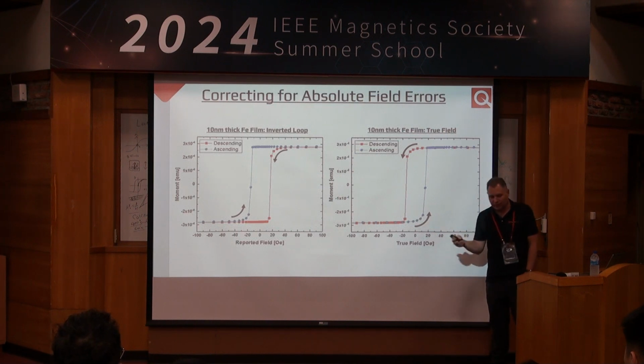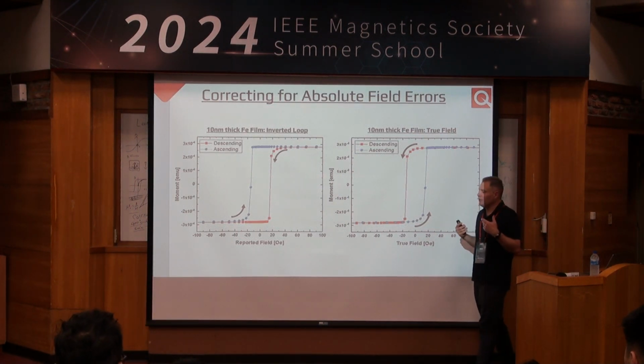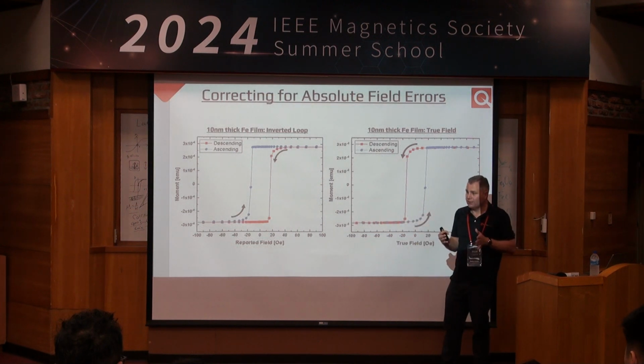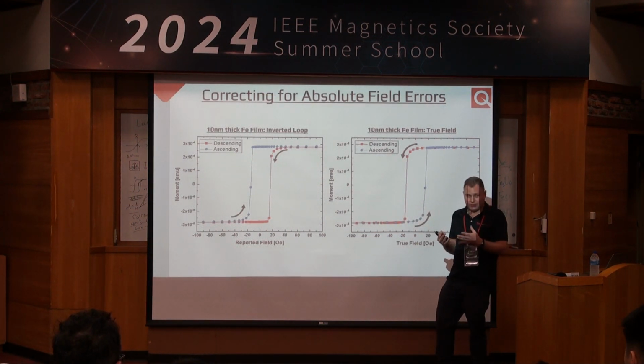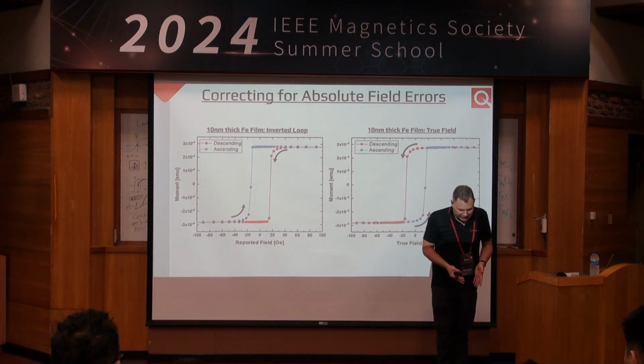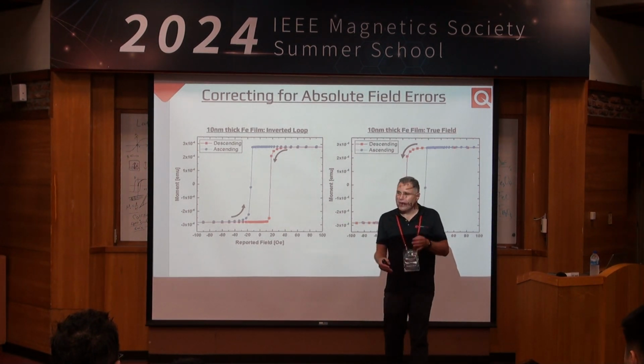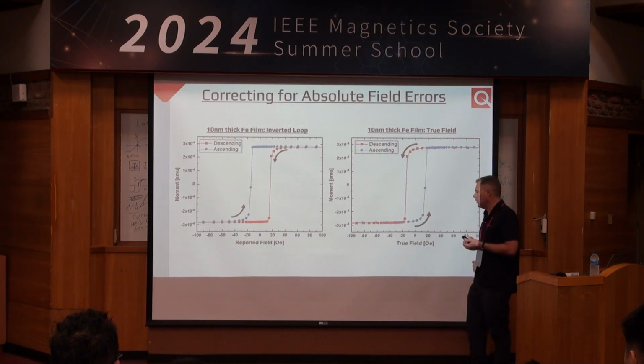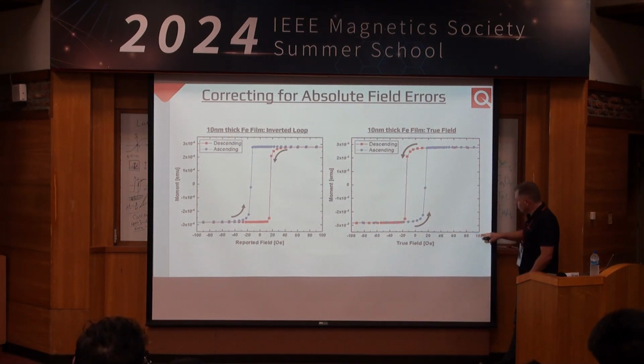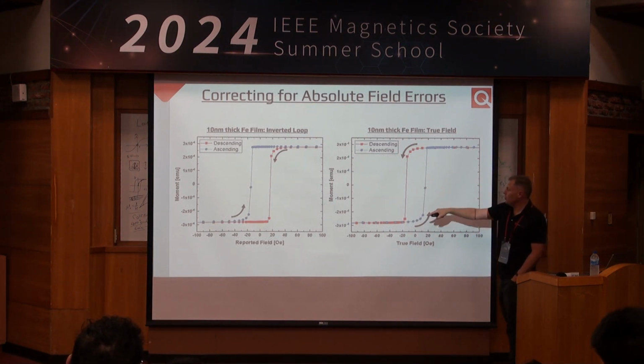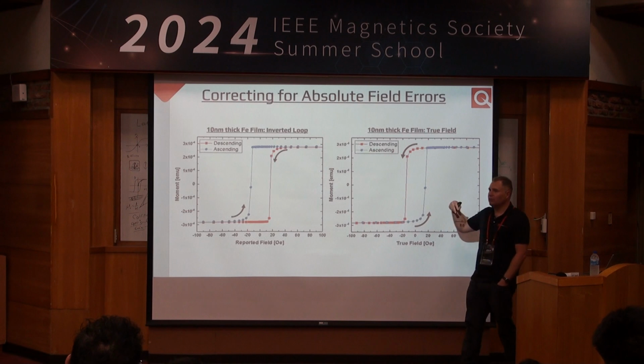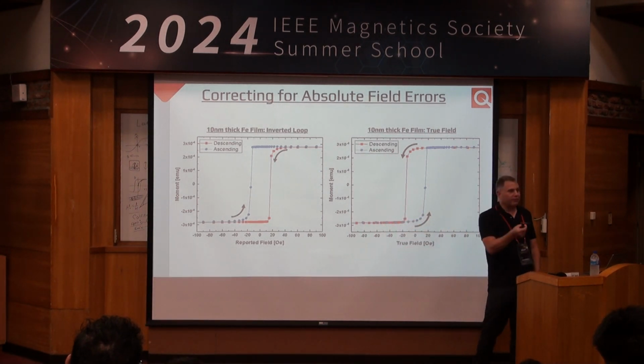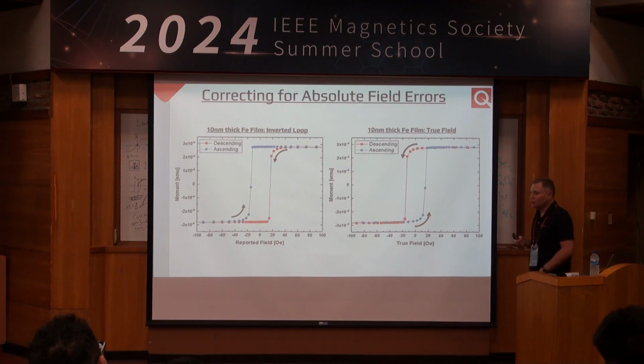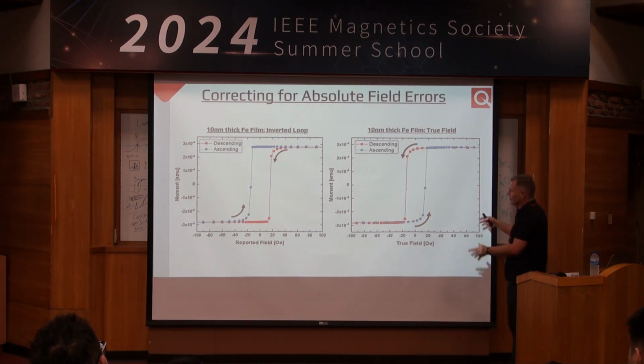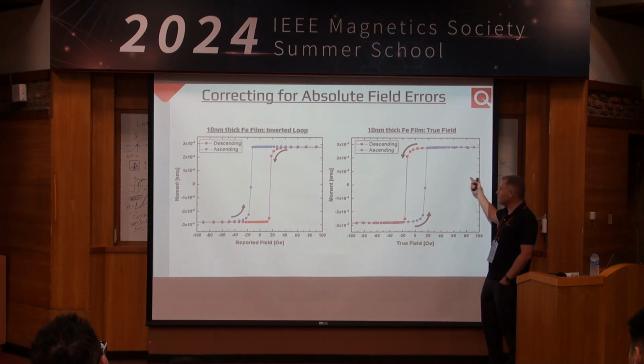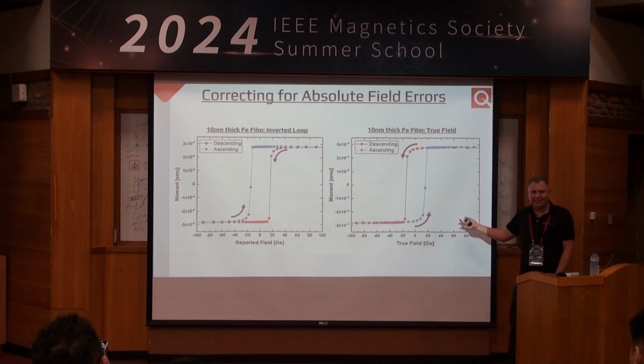So this is a very important thing to keep in mind, and it's really only an issue when you need to measure at large fields and small fields. So you can get rid of the magnetic flux in your magnet by first setting a magnetic field of 3 Tesla and oscillating the field back to 0. That'll get you a remnant field on the order of an Oersted or so. And if I was to measure just between plus minus 100 Oersted, my loop would look like this. But the second I start to approach half a Tesla or more, that remnant field will come back, and I have to account for that. So it really is only an issue if you need to measure small and large fields. Honestly, why would I measure this all the way out to 2 Tesla? It's clearly saturated, right? Why would I do that? I did it as an example here.